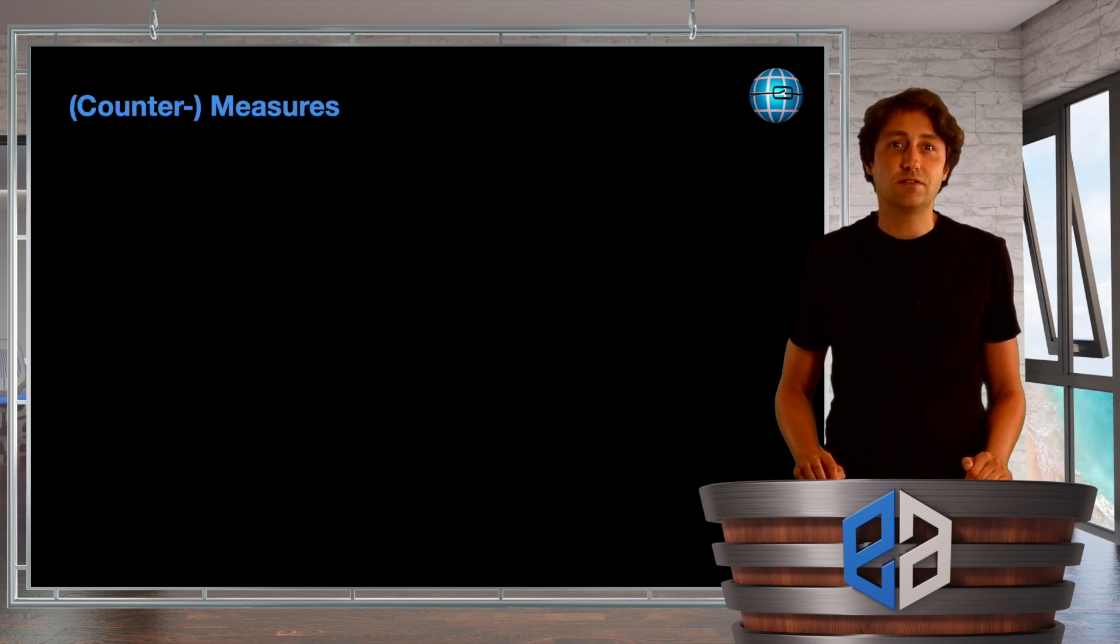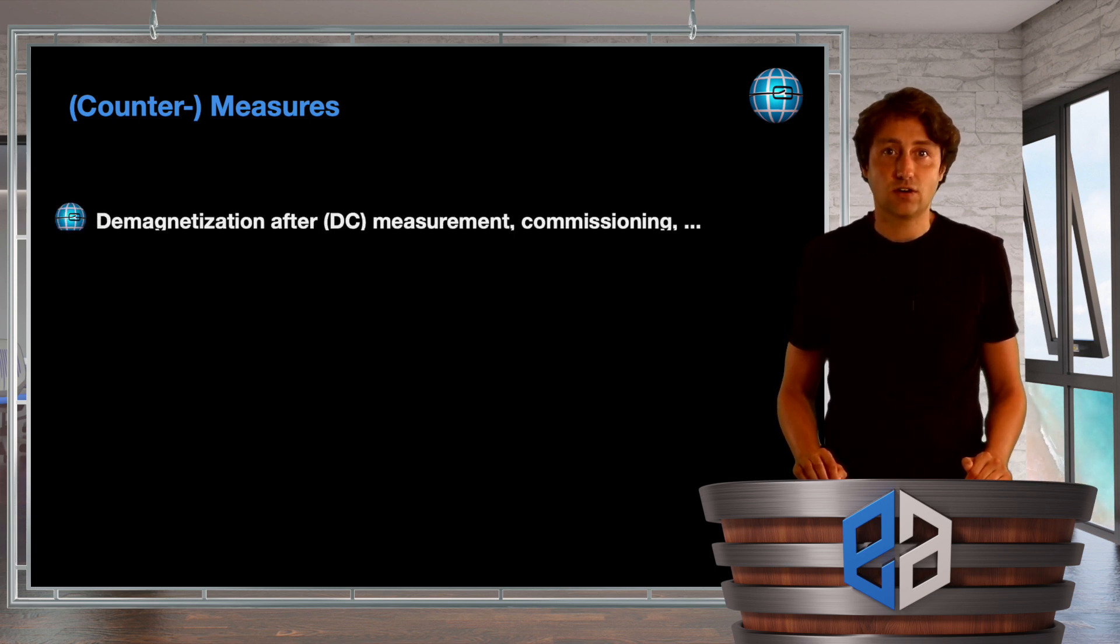Now what are the countermeasures that we can take? Firstly it is highly recommended to demagnetize the core after each DC measurement, which modern current transformer measurement devices can perform. It's a special function.